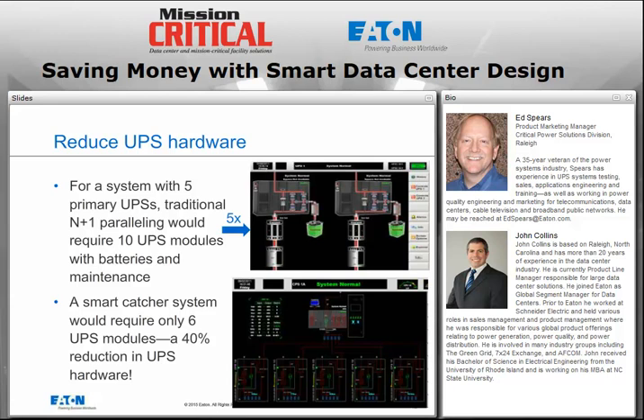Smart Catcher system, as you see in the bottom portion of the screen, where I have a catcher UPS here, if you can see my cursor, and it is providing the bypass source for 5 primary UPSs that do not have to be the same size. They don't have to be installed at the same time.